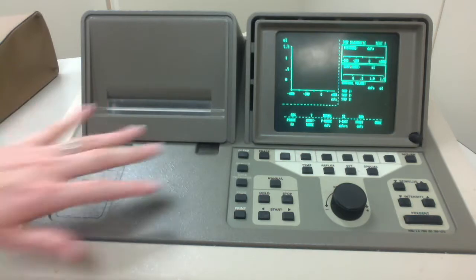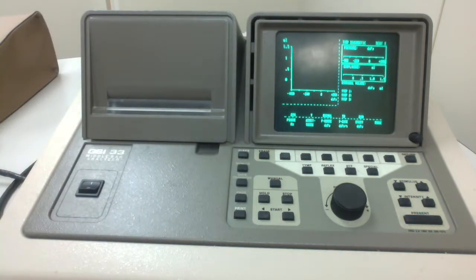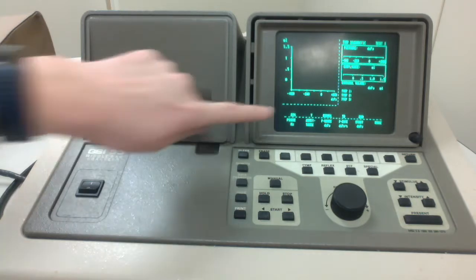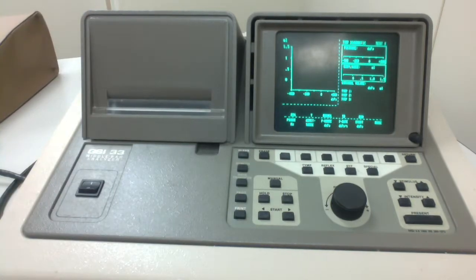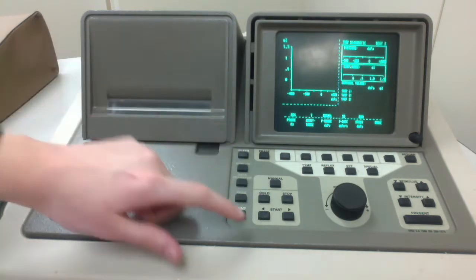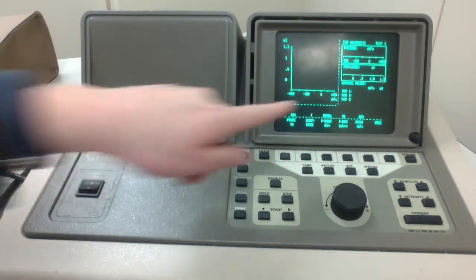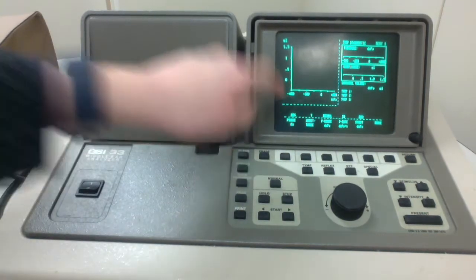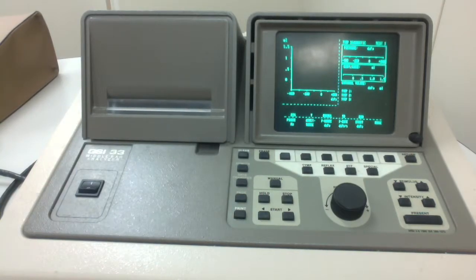So for tympanometry, the setting we're at right now, it tells us about how well the eardrum moves as a function of pressure. Our measurement will give us three things. It gives us ear canal volume, peak pressure, and then compliance, otherwise known as static admittance. We'll be testing at 226 hertz because we're all adults, but if we were testing pediatrics or under the age of 6 months, we would be using 1000 hertz. So when we go to test, we click this start arrow with the arrow to the left, and that means that it's going to sweep in pressures to the left. So we'll be going from 200 positive decapascals to negative 400 decapascals. And that pressure is what's being applied to the ear. And then along the y-axis, what we're measuring is compliance or admittance in milliliters. And then it'll be plotted on that graph.